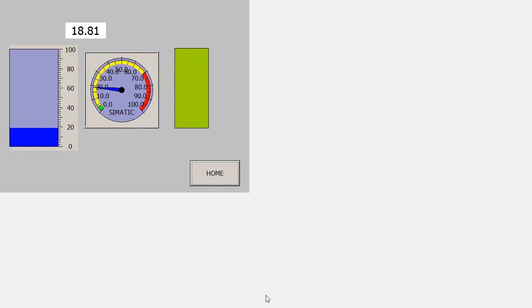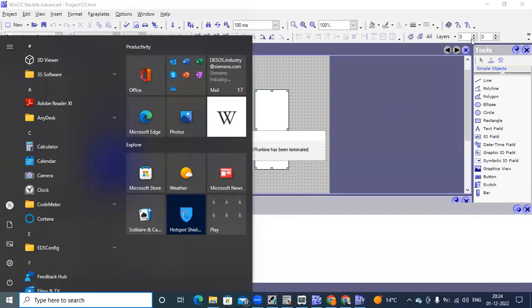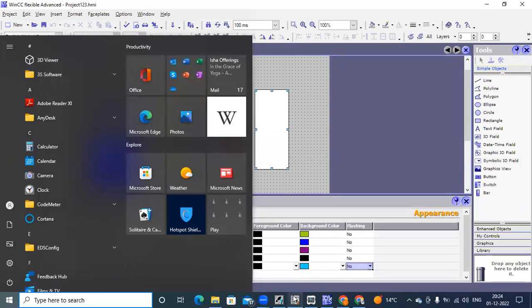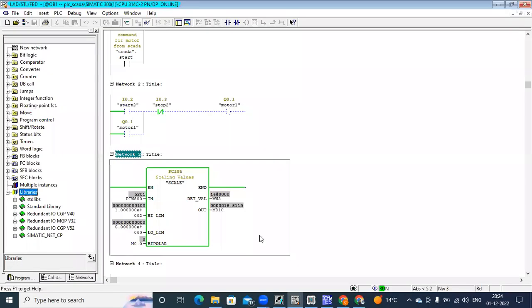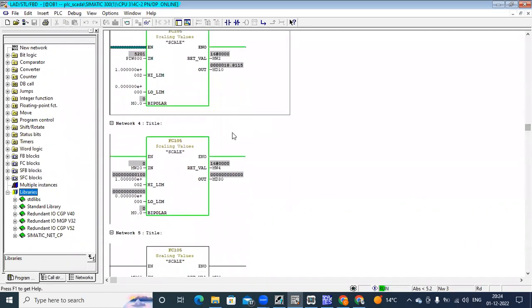Now, suppose if I want to use a slider from HMI, then you need to write a program in your PLC again, because you cannot directly control the I address of the PLC — you can access only the internal memory address of your PLC. For that, you have to use a code address. You can see already one parameter block available: mw20 for input and md30 for output.